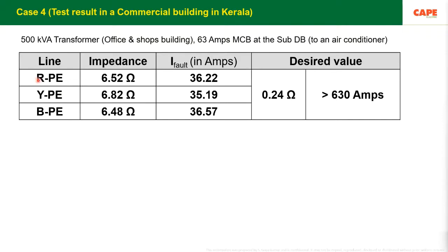The result which I got is R to P, R phase to earth impedance, is 6.52. The fault current is 36 amps. And you can see here the average earth fault current in that MCB was about 35 to 36 amps. Whereas this MCB requires 630 amps to trip within the specified time. So the current which is actually the earth fault current which is flowing is not even 5% of what is necessary. The current is very, very small. As a result, what can happen is if this air conditioner makes a fault, you can be sure that the result is fire or an accident.